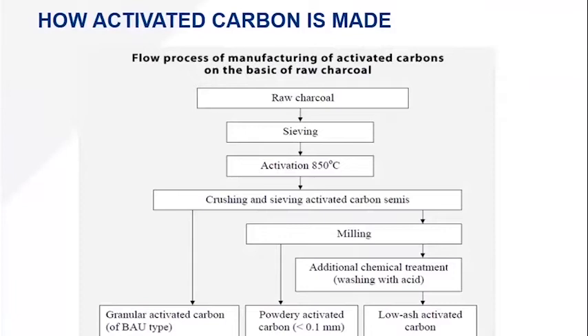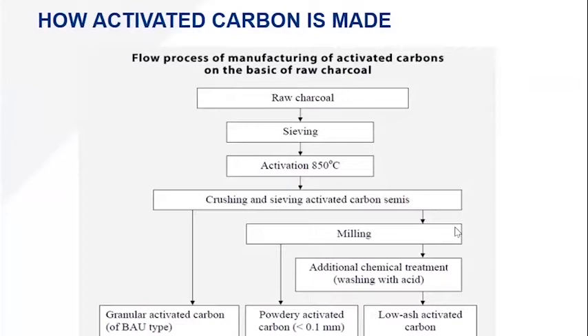For chloramine removal, what's going to happen is you skip the initial milling step, go to the acid wash chemical treatment, then take this carbon, remill it, and reactivate it. This will happen four to seven more times to produce chloramine carbon. What this does is produce exponentially larger numbers of activated sites on the carbon — a logarithmic scale increase in the number of activated carbon sites for chloramine removal.